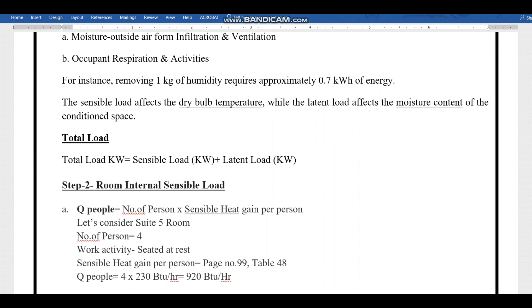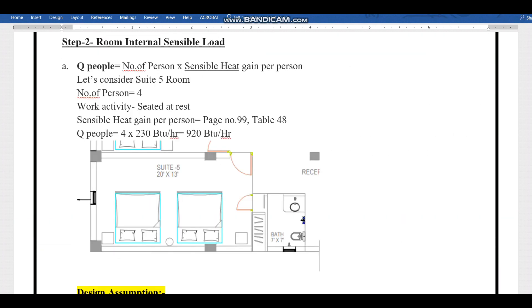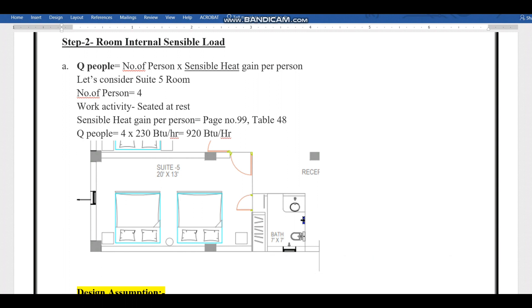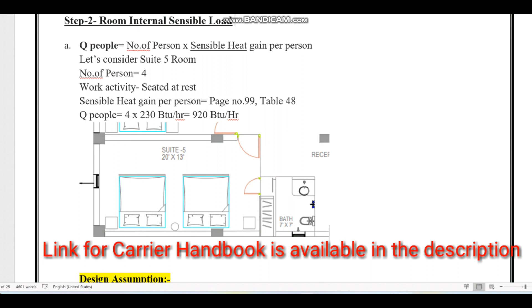Now let's start the calculations. Step 2 is the room internal sensible load. The first factor is people. In our example, we consider Room 5 from the architectural layout — a hotel room with four single beds for bachelors. So the number of persons is four. The worker activity is 'seated at rest.' Based on activity level, the sensible and latent load values change. We refer to Page 99 of the Carrier Handbook.